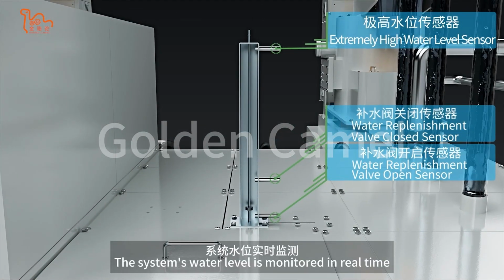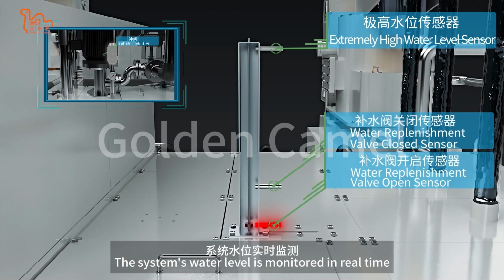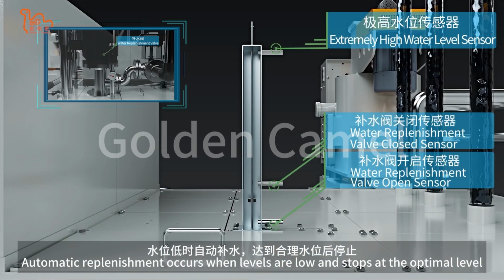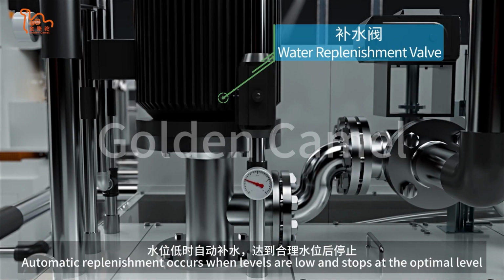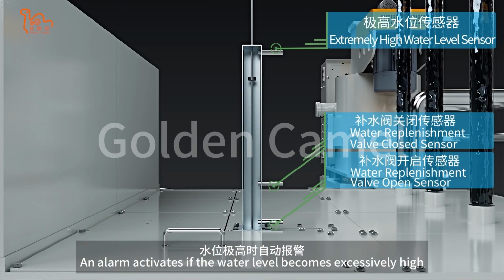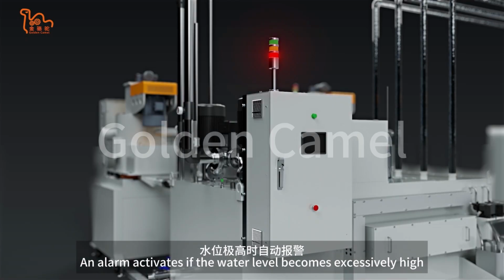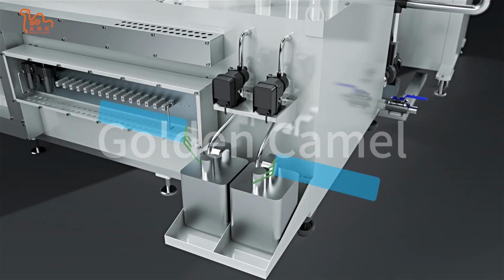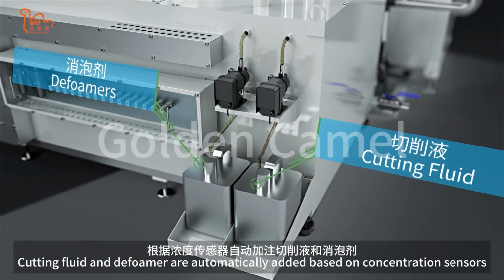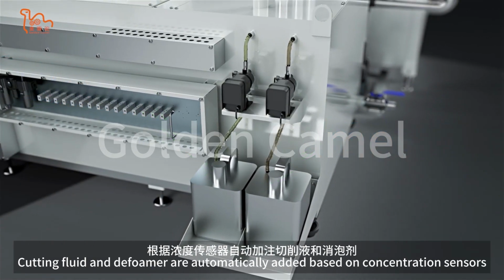The system's water level is monitored in real time. Automatic replenishment occurs when levels are low and stops at the optimal level. An alarm activates if the water level becomes excessively high. Cutting fluid and defoamer are automatically added based on concentration sensors.